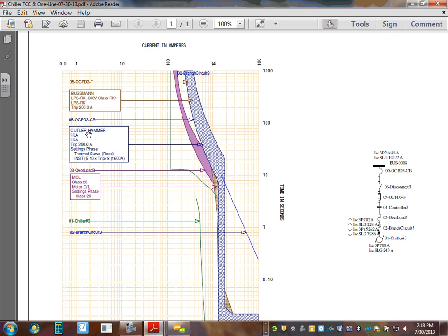And if you have an adjustable circuit breaker or a dual element time delay fuse, you can do a great sizing and great coordination with only 1.25. Even though, remember, you are allowed to use the maximum overcurrent protection device from the manufacturer. You don't have to use it, but you can use less than the maximum overcurrent protection device from the manufacturer if you do analysis on this.